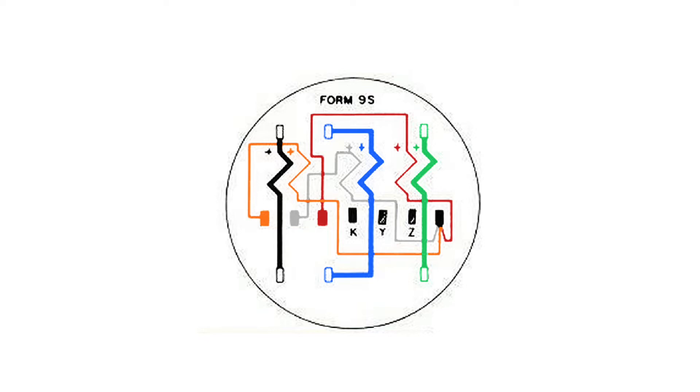We also see on this meter a KYZ. KYZ is a value for each pulse and we tell the customer what the value is of each pulse and they can either monitor their load or they can control their load off this value.